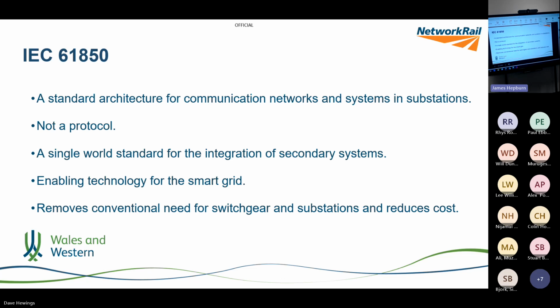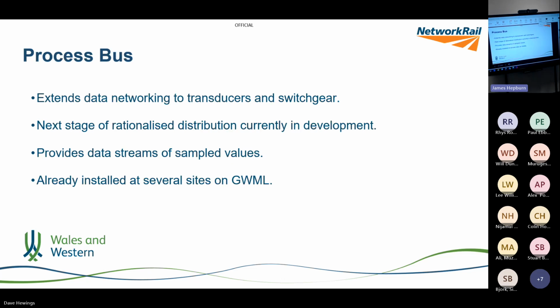The world's moved on from that, because instead of just having IEDs, there is now another layer of bus that has moved on since Great Western. This is moving so fast that Great Western is now old. So that extends data networking down to transducers, current transformers and voltage transformers, which are really the eyes and ears of a power system. That's where you get your information: what's the voltage doing, what's the current doing. You would wire them into the IEDs, and then the data would go.